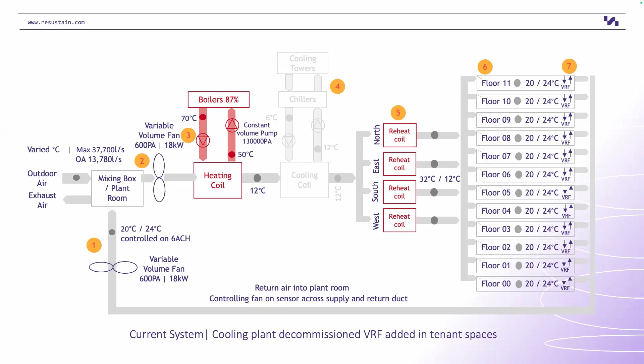We actually found that the outdoor air damper was fixed open. So all of that was outdoor air coming in. Then we got our boilers at 70 degrees, a fairly standard hot water temperature. Our heating coil in the air handling unit was coming off at about 12 degrees, so it wasn't really doing much in the air handling unit, and then the reheat coils were set to 32 degrees. But what was really interesting about those is that their valves were actually sort of stuck open. As I said, this is a 50-year-old system, so not that surprising. So some of that air was coming in at 40, 45 degree temperature. So then the VRFs had to work with those kind of temperatures coming in at them. So we found quite a lot of conflicts already.